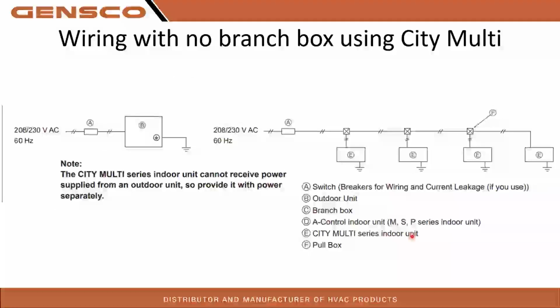For City Multi indoor equipment, that cannot be powered by the heat pump. You have to run its own dedicated circuit for that. You can't have multiple equipment off of a single breaker, which is fine. You just have to size your system accordingly. I do recommend having an indoor disconnect switch at each indoor head though. So with this, again, this is without a branch box using City Multi equipment.